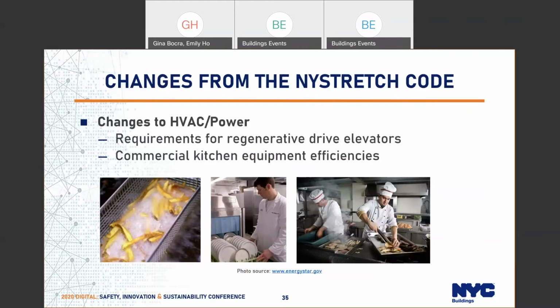All right, and moving on to HVAC and power. So one of the requirements is that, we are adding a requirement for elevators. It's only in new construction. So if a new elevator shaft is created in an existing building or under new construction, and the shaft height is greater than 7 stories, the elevator must be a regenerative drive. So, essentially when an elevator goes up with a light load, down with a heavy load, the system generates more power than it uses.